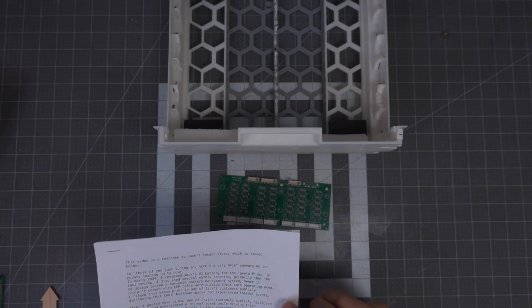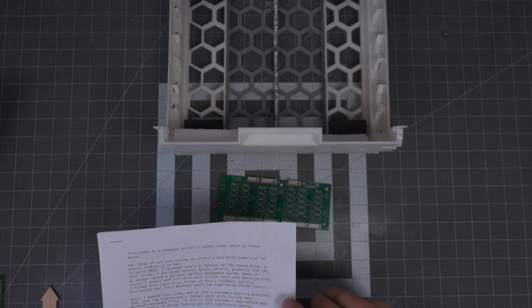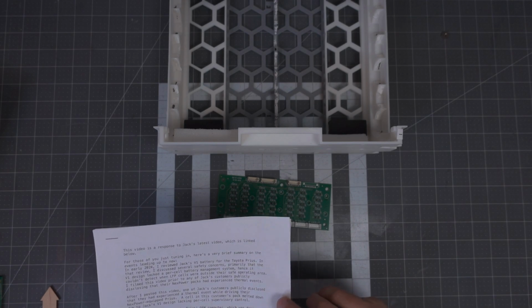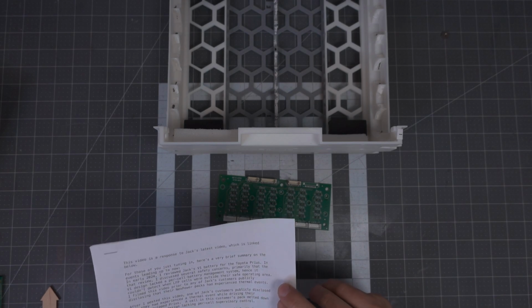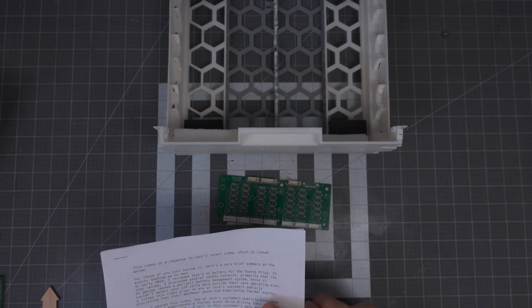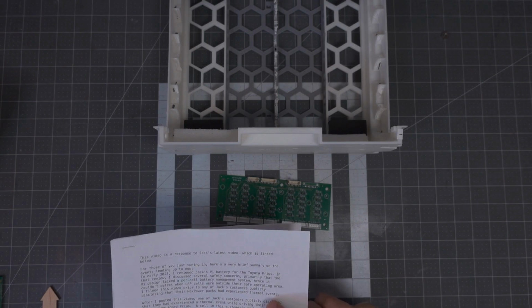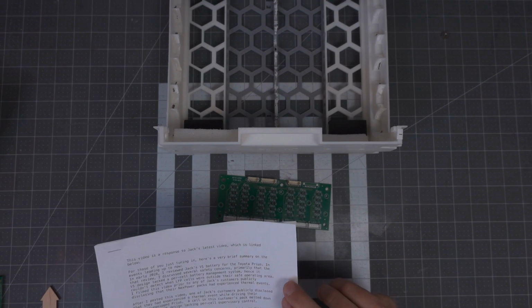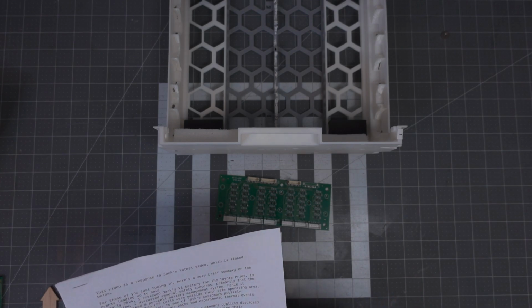In other words, by the time the OEM computer detects a failing cell, that cell is already well outside of its safe operating area. A compounding factor is that both lithium and sodium cells are considerably more energy dense than nickel metal hydride and are much more susceptible to thermal runaway.